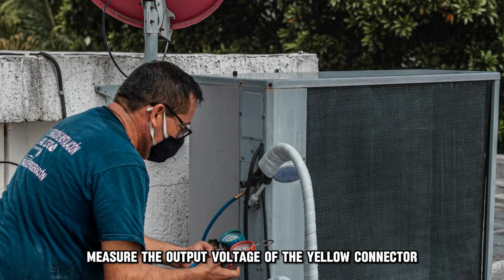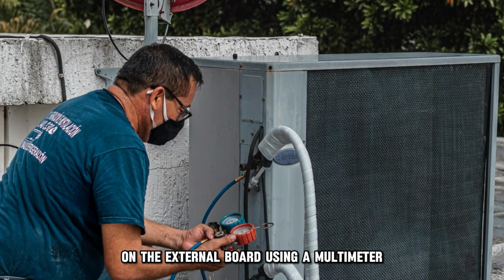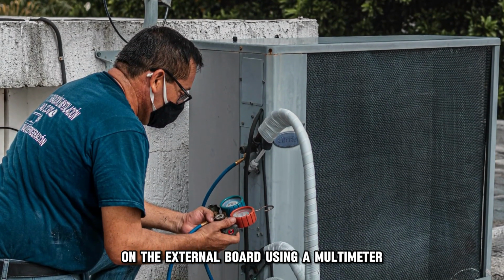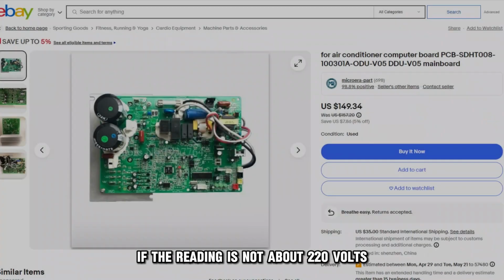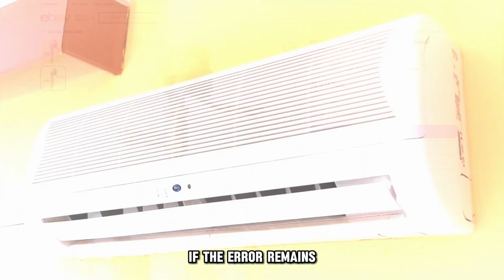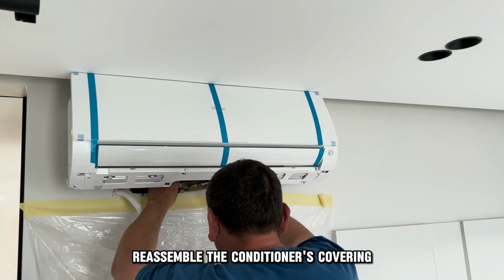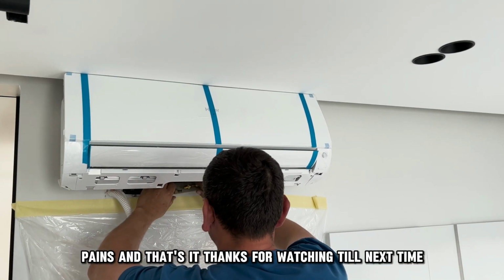Measure the output voltage of the yellow connector on the external board using a multimeter. If the reading is not about 220 volts, replace the board with a new one. If the error remains, replace the expansion valve with a new unit. Reassemble the conditioner's covering panels, and that's it.